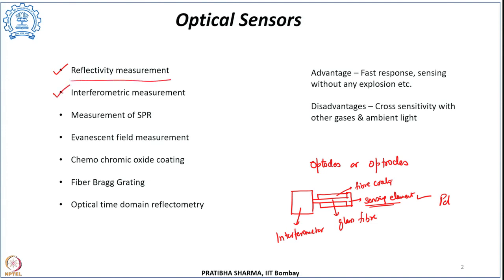The second method is interferometric measurement. In this approach, there is a change in the dimension or refractive index of the gas sensing material when exposed to hydrogen. That change causes a phase change in the fiber optic beam, which is measured using interferometric techniques. Different interferometers can be used, such as the Michelson interferometer or the Fabry-Perot interferometer. This change is correlated with the gas concentration.